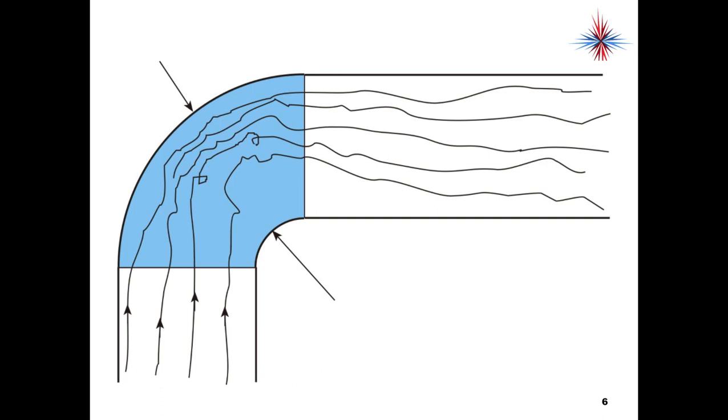The air acts much the same way in a radius throat elbow, especially if the throat radius is too small. If it's too tight at the throat radius, I'm still going to have all the air hitting the heel, bunching up there and not being smooth through there. So I'm restricting airflow even though the duct inlet and outlet are the same size.